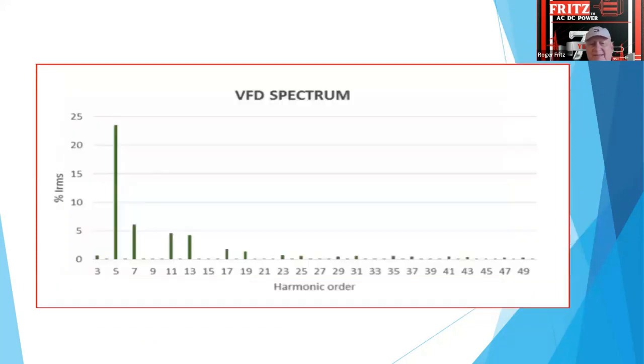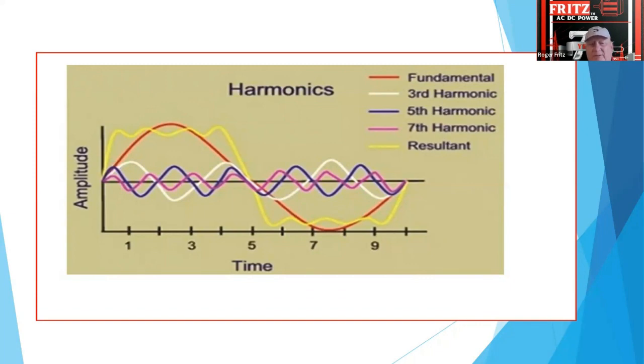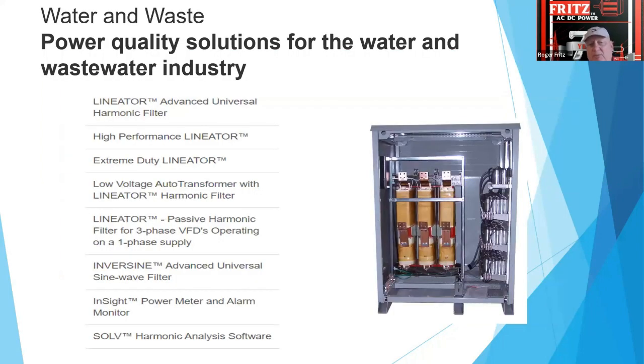So again, this is what they call the fundamental, which is what the voltage is here. The resultant is what the power company bills you here for load power. So you can see as we get these various harmonics, and a lot of this happens in heavily inverted lighting, DC machines give off a lot of different amplitude, various harmonics out there. And so what happens is, by this being off, the resultant power is quite a bit higher.